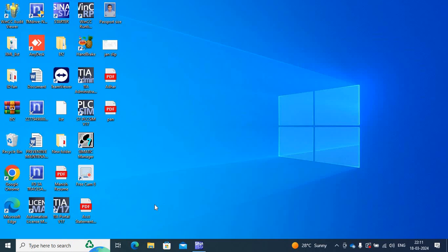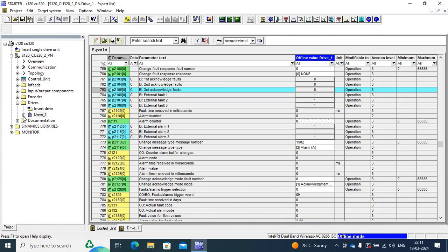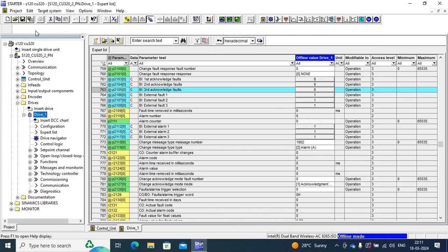Dear friends, today my topic is how to configure fault into alarm in Siemens drive. So open the STARTER software and go to the drive. This applies to S120, G120 and all Sinamics drives.